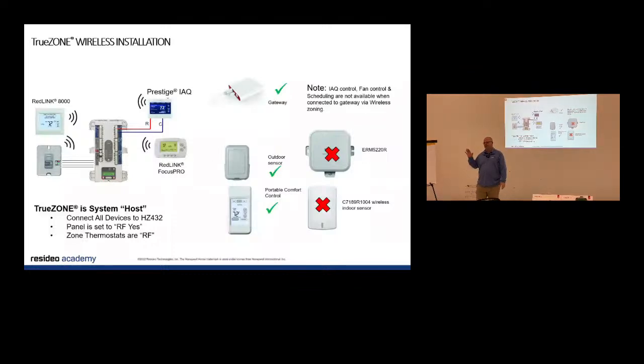The reason the adapter is separate is because not everyone's going to need it. So why would I put another $40 into a panel if I don't really need it? So new construction, you don't need the wireless adapter. Change out, you're going to need it, although with cost of labor and wire, I can almost argue this would work better in new construction, but that's an argument between me and the contractor, not you guys. So the wireless adapter, basically 4 wires into the panel, and then I can talk to all the way up to 4 thermostats wirelessly with that panel.